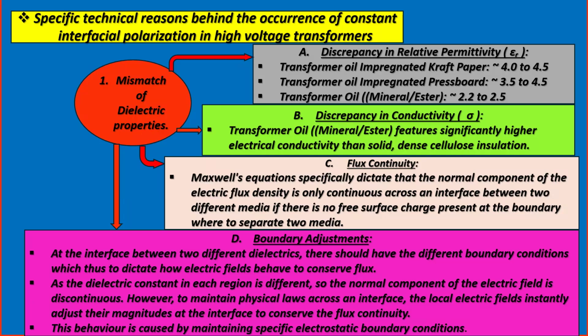A. Discrepancy in relative permittivity. Transformer oil-impregnated kraft paper: 4 to 4.5. Transformer oil-impregnated pressboard: 3.5 to 4.5. Transformer oil, mineral or ester: 2.2 to 2.5. B. Discrepancy in conductivity. Transformer oil, that is mineral or ester, features significantly higher electrical conductivity than solid, dense cellulose insulation.